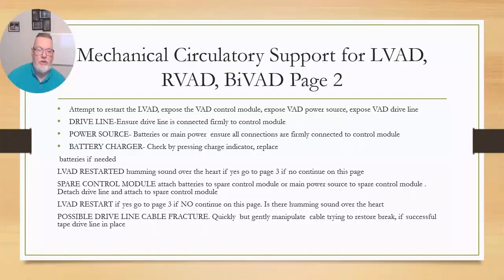Drive line: ensure the drive line is connected and firmly in the control module. Batteries or main power: ensure all connections are firmly connected to the control module. Battery chargers: check by pressing the charge indicator. Replace batteries if needed. LVAD restarted.